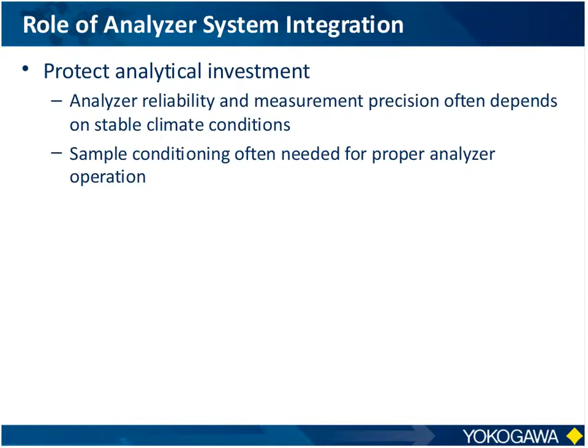Quite often, these analyzers are not always meant to be installed outside in the weather, and more importantly, they may not be designed to operate in hazardous or explosive environments typically found in a refinery or chemical plant. Also, most analyzers can't directly sample the process sample itself without some type of conditioning, either to bring it into the right temperature or pressure range, or perhaps do some filtering or flow adjustments. So often extractive type analyzers, which would be installed in a shelter or box or cabinet, need some type of sample preparation or sample conditioning as part of the total package.